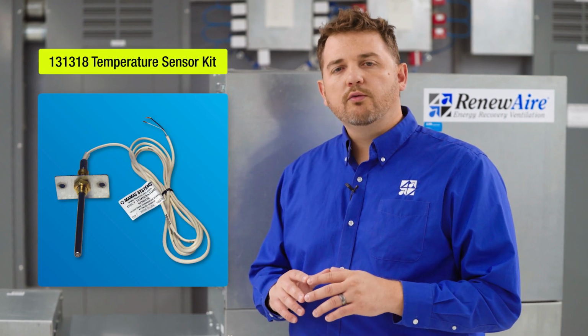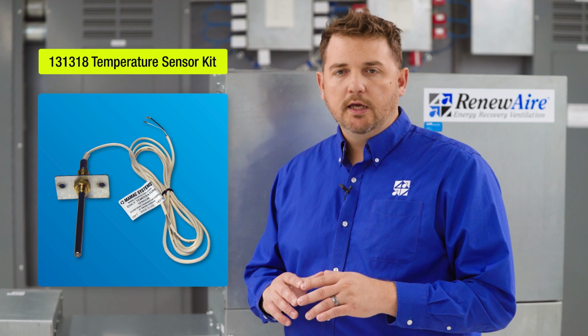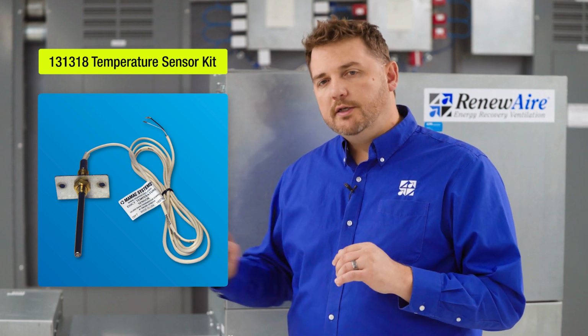We will now discuss controls. For applications with premium controls, the 131-318 temperature sensor kit is required and should be mounted downstream of the coil module. As a rule of thumb, install the sensor at least 3 duct diameters downstream from the coil module.